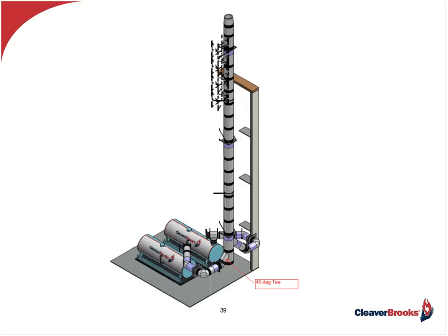Now, using the draft calculation that we just performed as a starting point, we're going to consider changing that 90-degree T in the original engineer's layout to a 45-degree Y that we're showing here at the bottom.